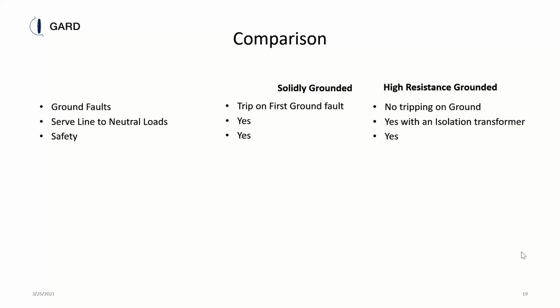This is why when you specify a variable frequency drive or adjustable speed drive or a surge protective device, you must tell your contractor, your distributor, you need a 480 volt or 600 volt surge protective device capable of handling 200 kA, designed for an X grounded system. And that X grounded system is going to be solidly grounded if you have a solidly grounded system, or it's going to be high resistance grounded if you have a high resistance grounded system. So the high resistance grounded device will work on the solidly grounded system. The solidly grounded device, unfortunately, will work on the resistance grounded system, but not the way you want it to.